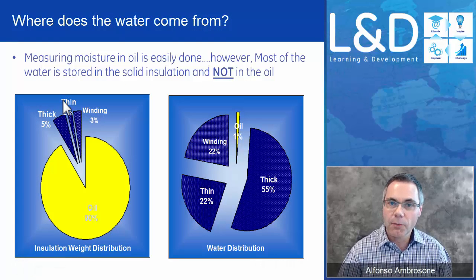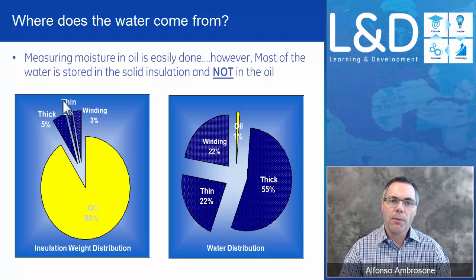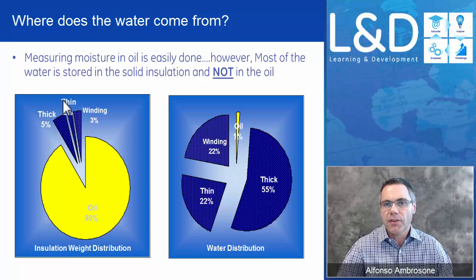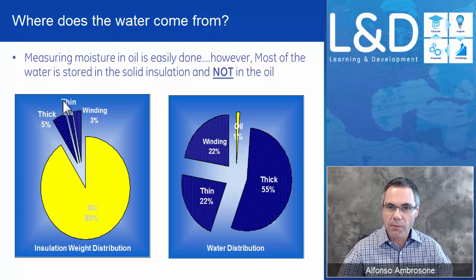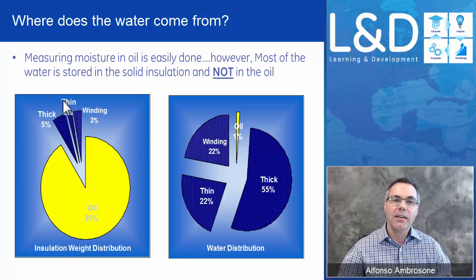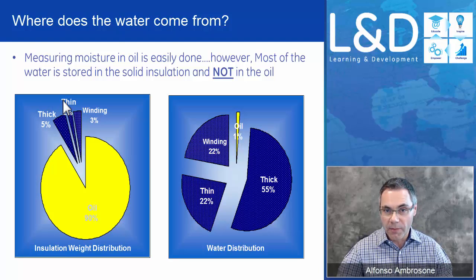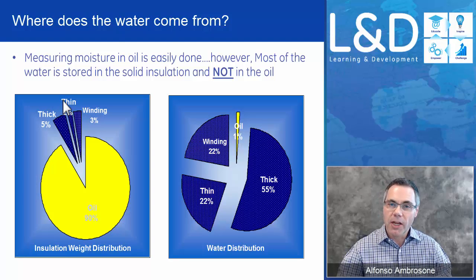Let's have a look at this moisture. Here are two pie charts. The pie chart on the left represents the distribution of insulation — 90% of the insulation in a transformer is oil, and only 10% is paper. However, when you look at the relationship of water distribution, 99% of the water is actually in the paper, and less than 1% is in the oil. So that's where the water comes from — a breakdown of the paper bonds will generate moisture.